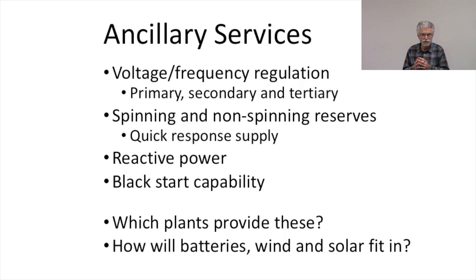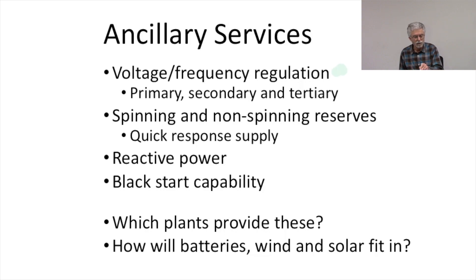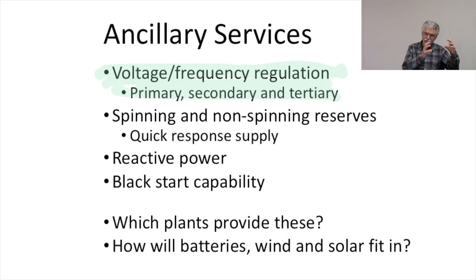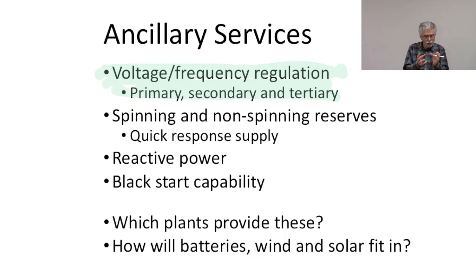Ancillary services are the services power plants can offer to help improve the performance of the transmission system. Probably the most frequently considered one is voltage and frequency regulation, which has to occur in the very short run, the medium time frame, and then in the longer time frame. So we have to have a whole range of these frequency regulation ancillary services available from our mix of generation assets in the grid.